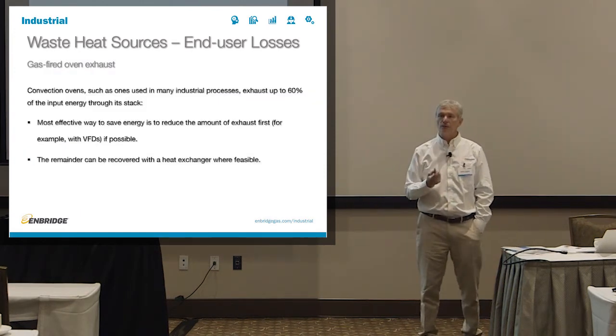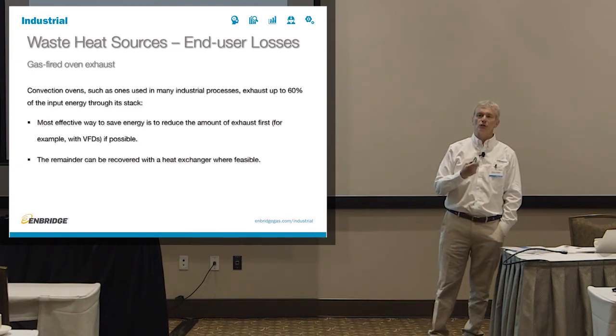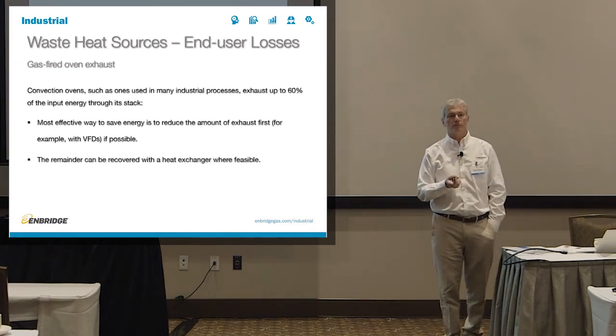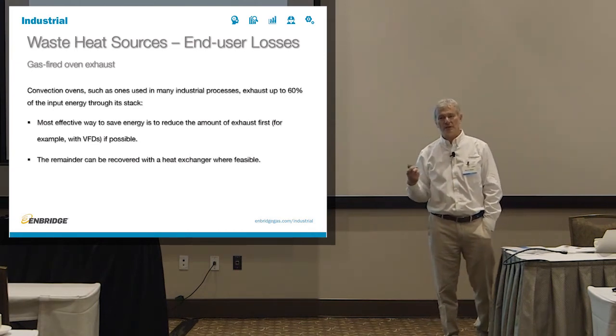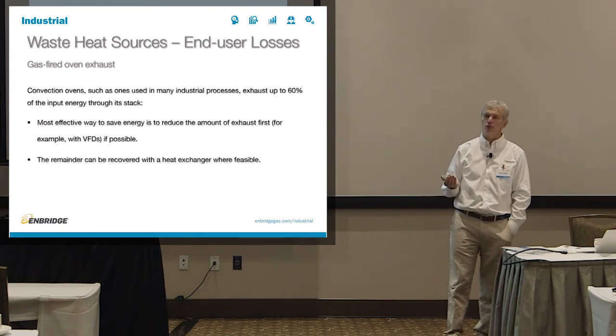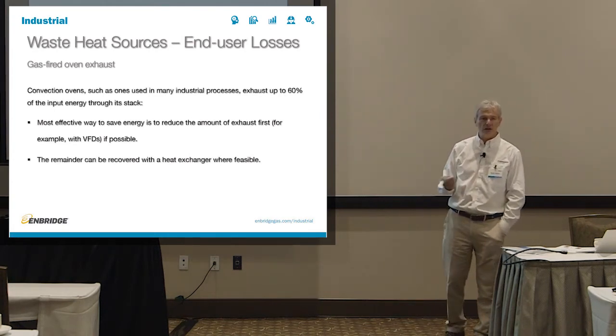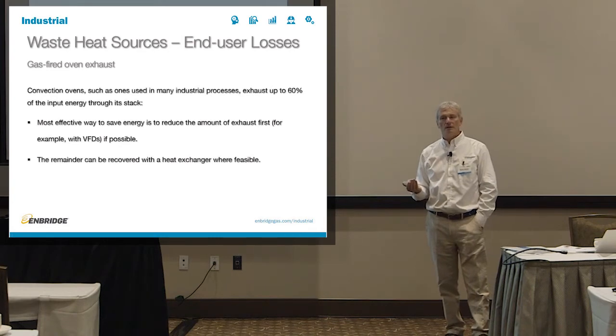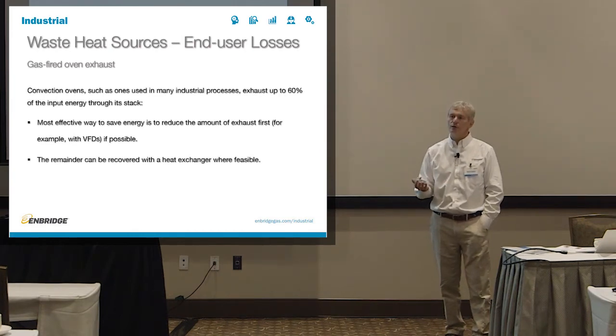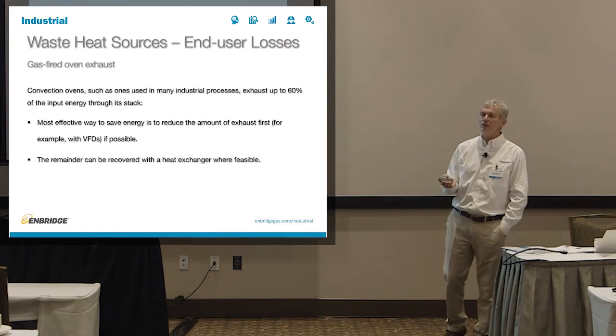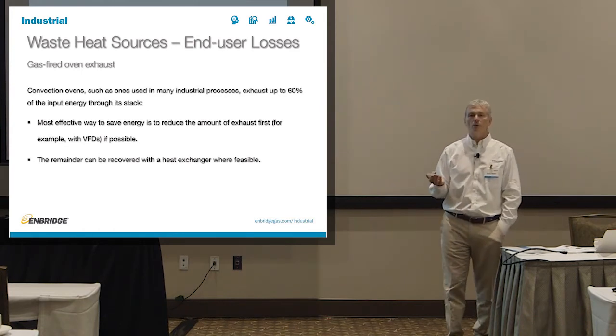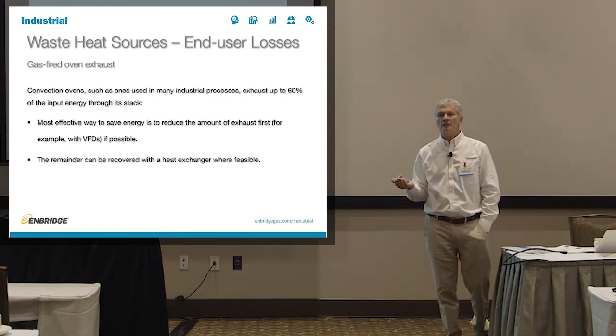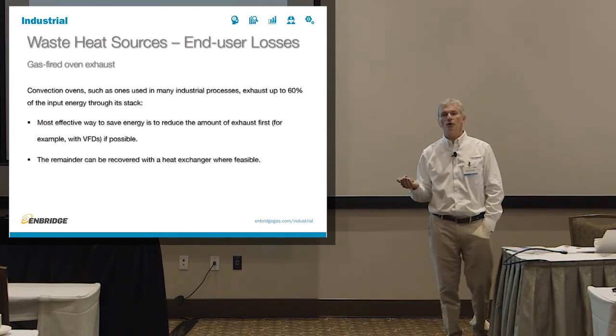So the most effective way to fight that is to put a VFD onto the oven exhaust. Nowadays, those exhausts are relatively small motors, and VFDs are very good price these days. So you can leave the operating purge mode at 100% exhaust. As soon as you get out of the purge mode, you go to whatever your oven requires. And your oven will typically require, what would you say, Paul? 30%, 20% of the purge volume?